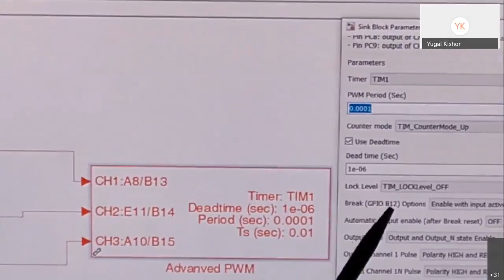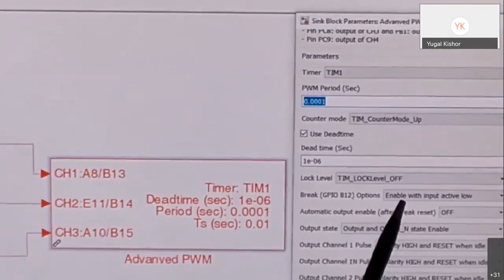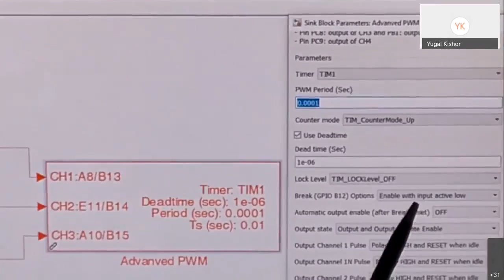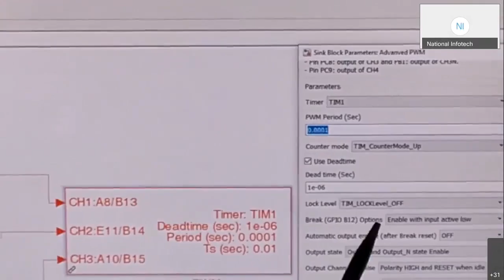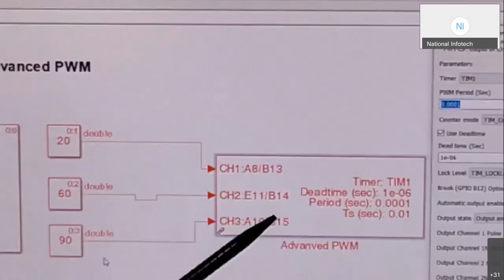Here I have already discussed that the break operation we can do using B12. The setting was enable with input active. So when we give this low pulse, meaning ground or zero magnitude voltage at B12, when we connect the ground of a circuit at B12, at that time all the pulse outputs coming from this will turn off immediately and go to the idle condition.